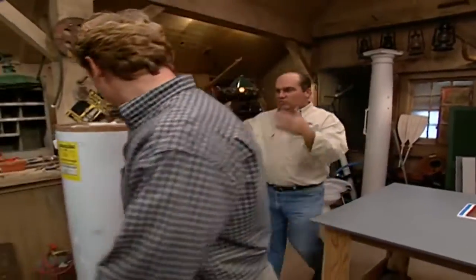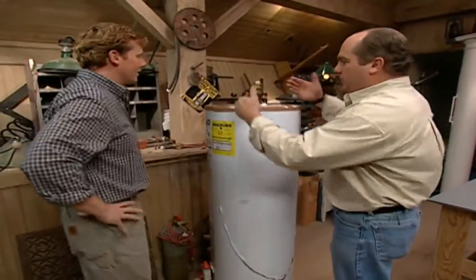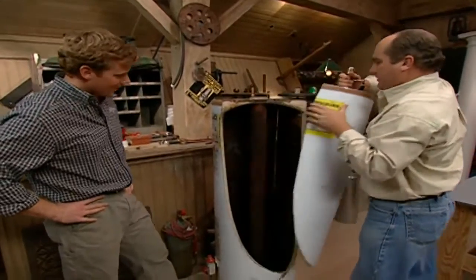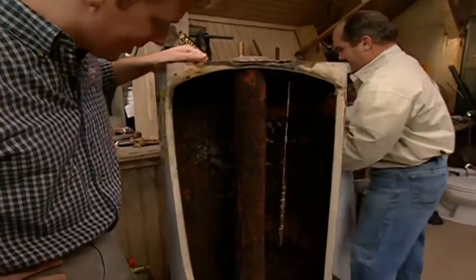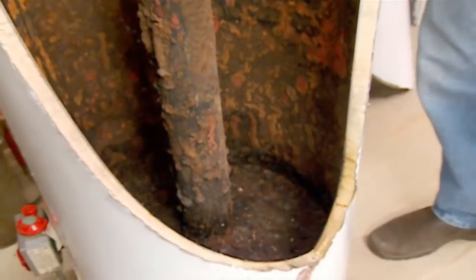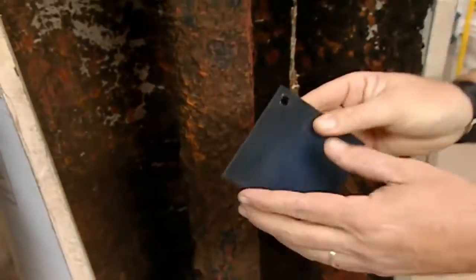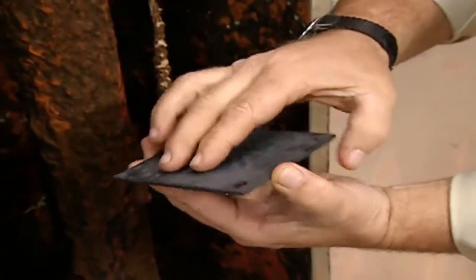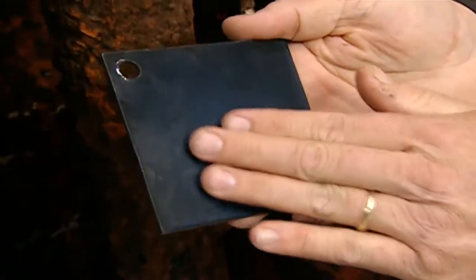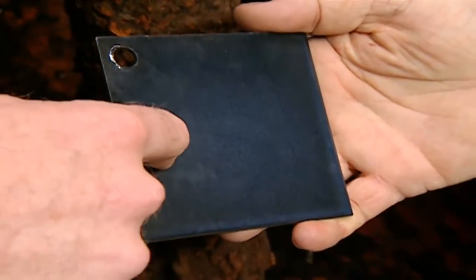So this is the actual water heater from that house. I took a saw and I cut it apart. Oh, Richard, this is horrific. That is horrible looking. What happened? Well, this is a glass-lined water heater, glass-lined steel, actually. The tank itself is made out of steel on this side, and on this side is this enamel coating. Oh, that's the glass they're talking about. That's right. That actually just kind of wraps around in here over the steel.